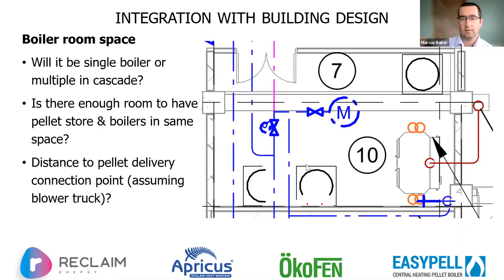So I just provided a little example here. This is from a Norman Disney Young design for a retirement village. And here we've got a 128 kilowatt Okofen boiler, and then the flue's just going to go out through the rear wall, have a bend, and then it goes up. This is a services cavity, a void, that will go up six stories to the roof. And this is a basement level. And we'll look at this as a project example a few times.